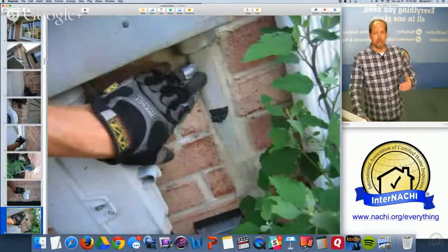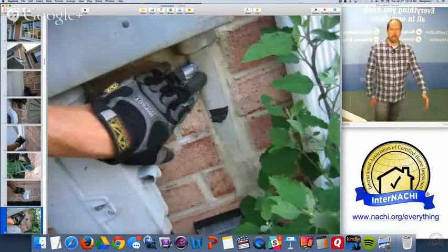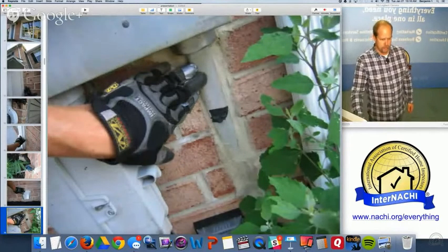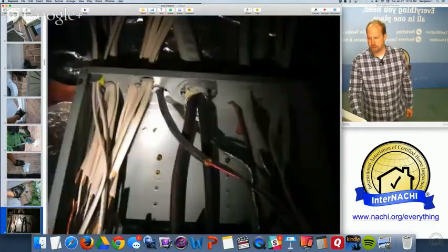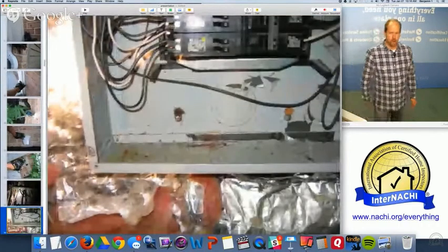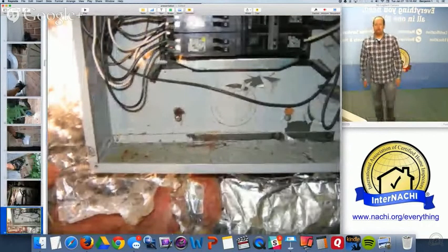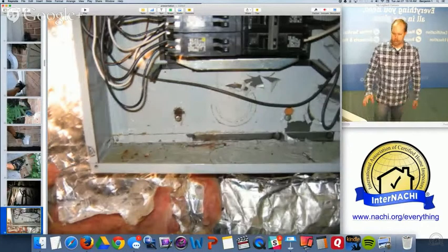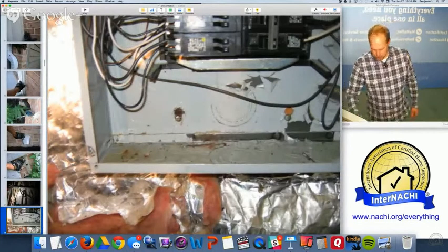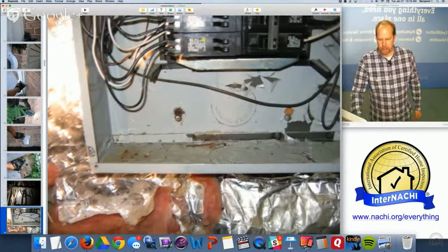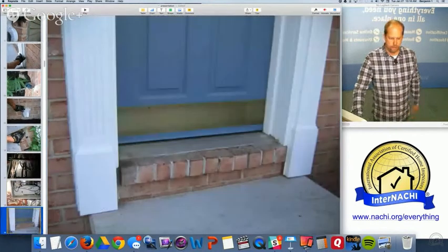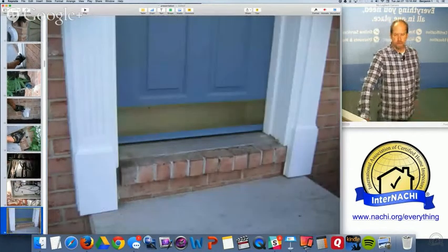And I follow the electric line. I tend to follow the electric line through the building materials into the house interior. That is sometimes a pathway for moisture intrusion. And in this home, we actually did have some water coming into the electrical panel. I observed indications of water intrusion inside the panel. You're not required to remove the dead front cover, but I did here. It actually caused rust inside the panel.